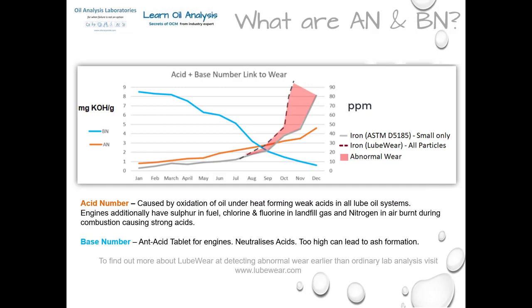It is a fine balance of timing and oil changes to get maximum life whilst protecting the engine. A few approaches include: an acid number increase above baseline by a certain value such as 1.5, a base number decrease by percentage such as 50%, or a threshold such as a base number less than two. Some use the AN/BN crossover point, while others look at the initial pH of around four or four and a half as the trigger. Changing oil earlier is possible but increases lubricant consumption costs.